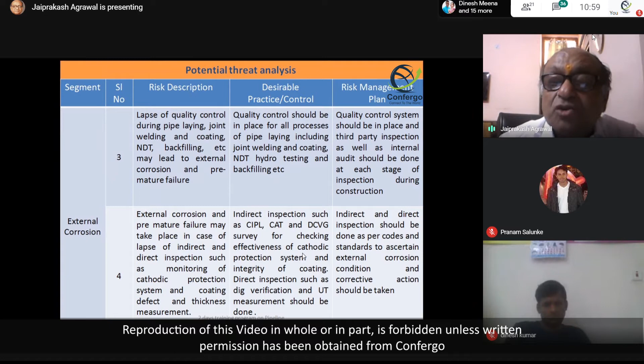And then there is indirect and direct inspection, so this is the monitoring in the O&M part, where we have to do CIPL, CAT, and DCVG surveys. So these are the desirable practices and controls. These are the three for the external corrosion, that you have to maintain proper inspection at the design stage, at the construction stage, and then at the operational and maintenance stage, to maintain the integrity so far as external corrosion is concerned. This is the inspection, monitoring, and testing which you have to do to control the external corrosion.